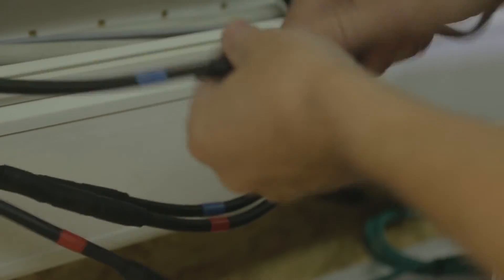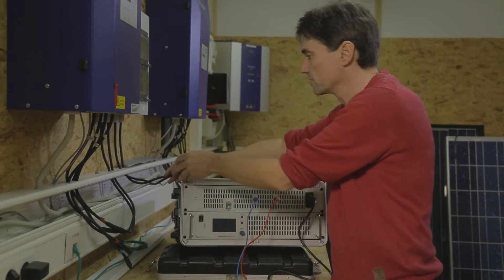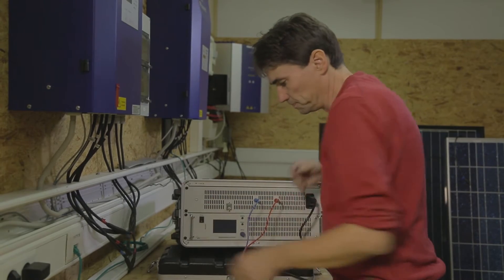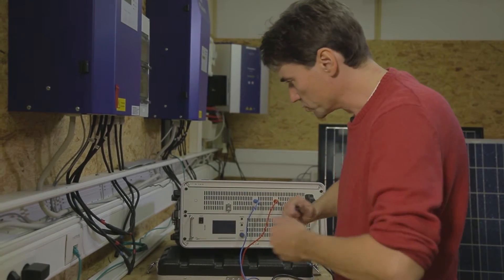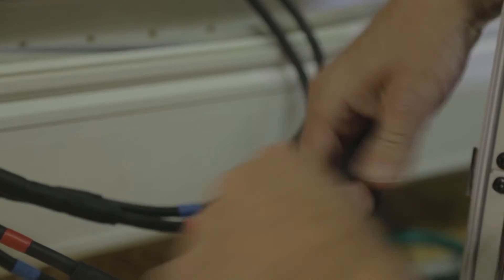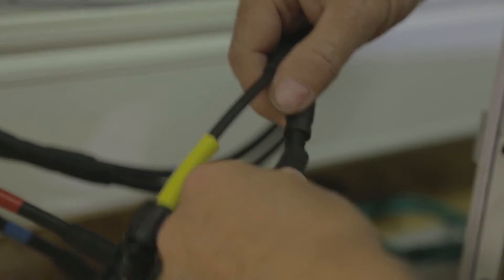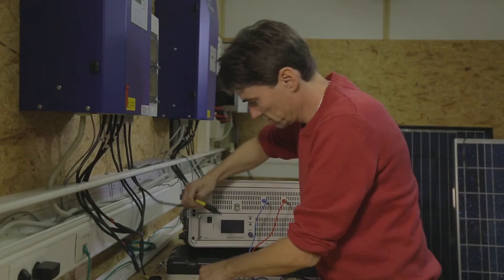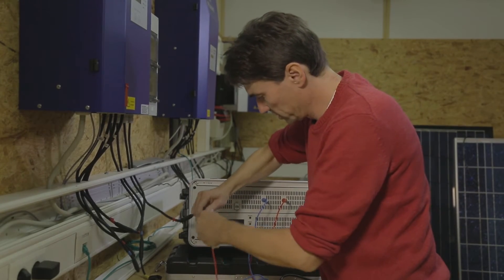This photovoltaic array still has the old MC3 multi-contact plugs. I'm now going to disconnect this string from the inverter, so I can send current back through it. To do so, I'm going to use the adapter that connects MC3 to MC4. I connect the solar array string to PVServe, which will send current back through the array.